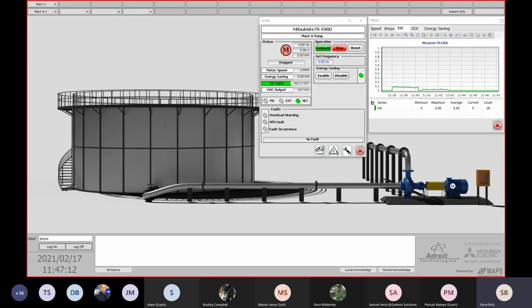But should you have an application where you need to run the motor between 0 Hz and 25 Hz, you're definitely going to require additional cooling on the motor. So always keep that in mind. Never run the motor below 25 Hz if you don't have force cooling installed on the motor. But yeah, the 5% setting, in the long term, has no impact on the motor. Installing a VFD onto the motor will prolong the life of the motor.